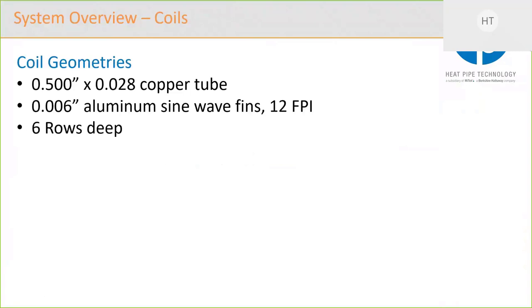So when I say sweet spot, what I mean is that as you add extra rows, you get diminishing returns. So you're proportionally increasing costs, but you're not proportionally increasing performance. Similarly, when you go to lower rows, it's cheaper, obviously, proportionally, but then your drop in performance is greater. So we found the sweet spot for our diameter tube and our sine wave fins is about 6 rows deep.